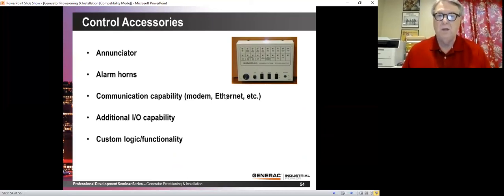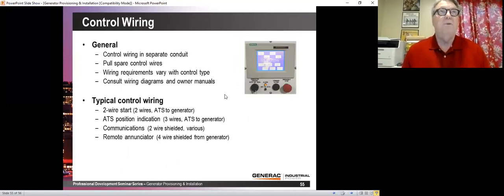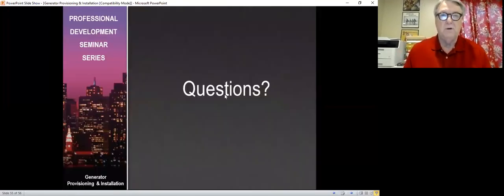If you need communications, communications is available on all NFPA 110 controllers, typically not available on the others, the residential and the light commercial. And here's some of your control wiring. 2-wire start is standard from the ATS to the generator.